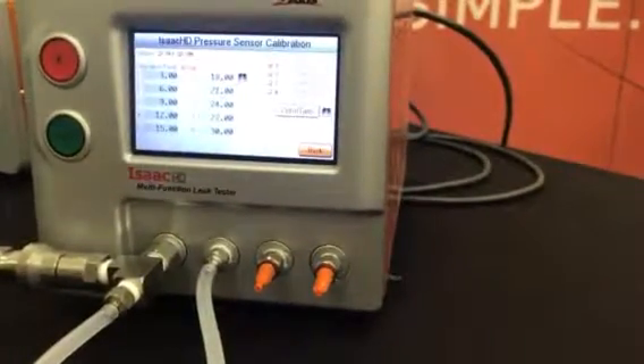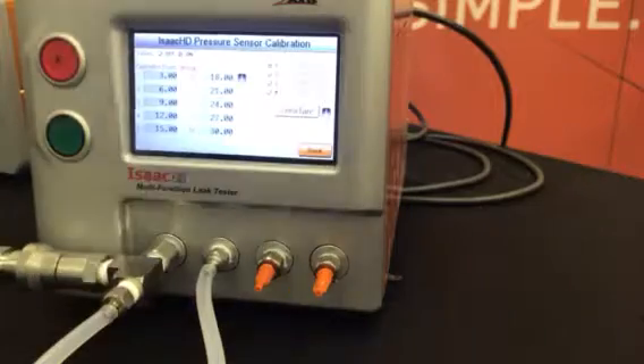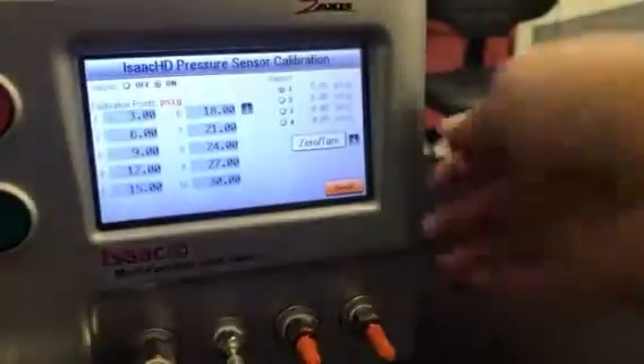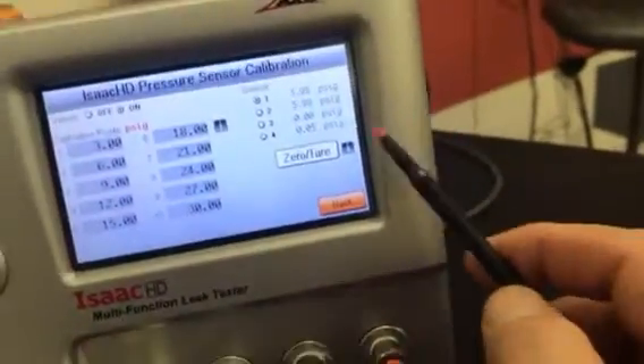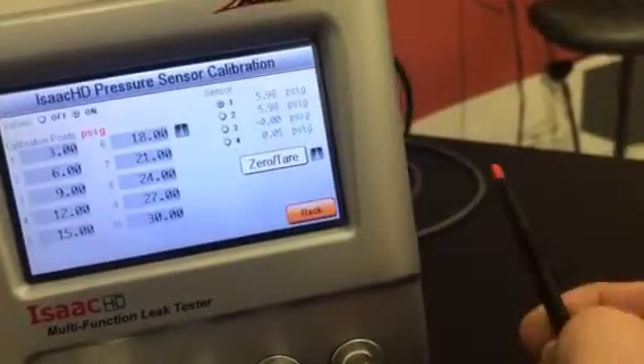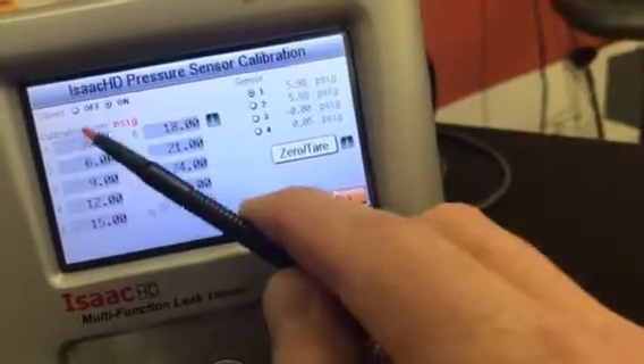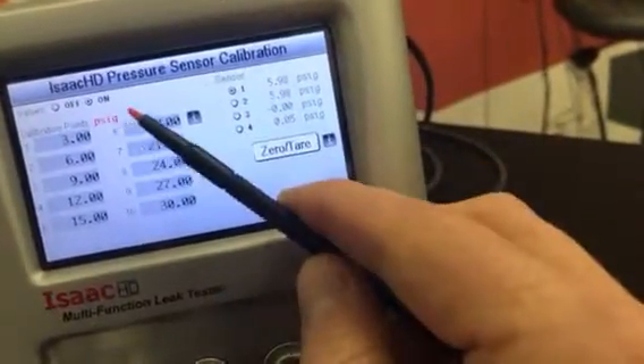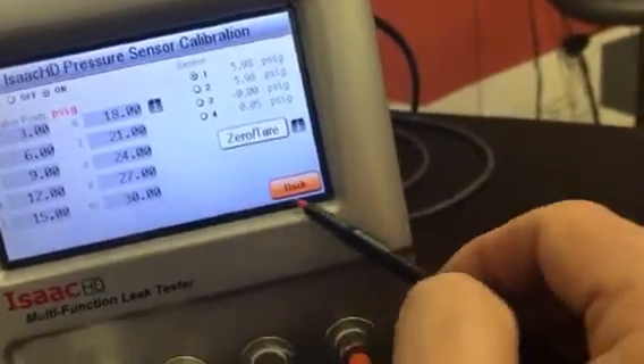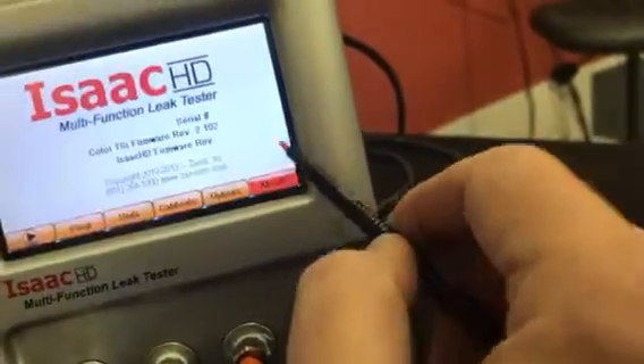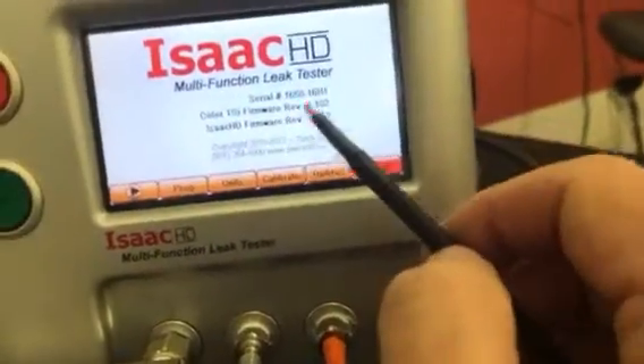Now, you'll probably need to do a tare on the pressure side and the vacuum side. It's good to do that just so the sensor knows what's an actual 0. So once you're all done with the vacuum, do the vacuum first, get all 4 cal points, then turn the valve off, go back into cal, do the pressure side like I was just doing. When you're all done, hit the back button, and now it's saved. So you should be good to go, and then you can go from there.